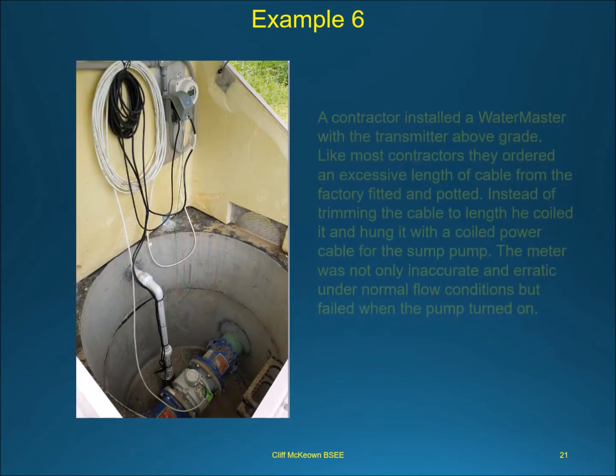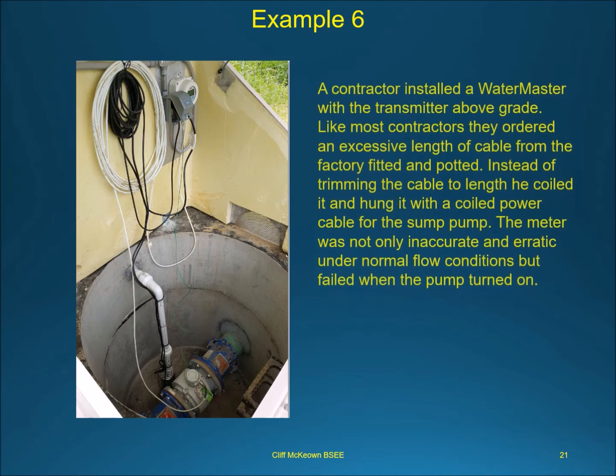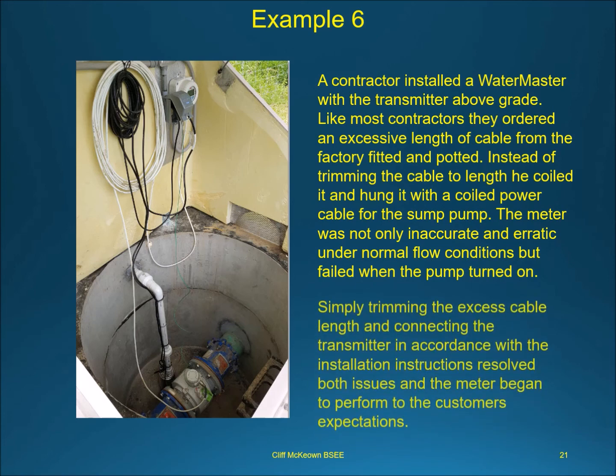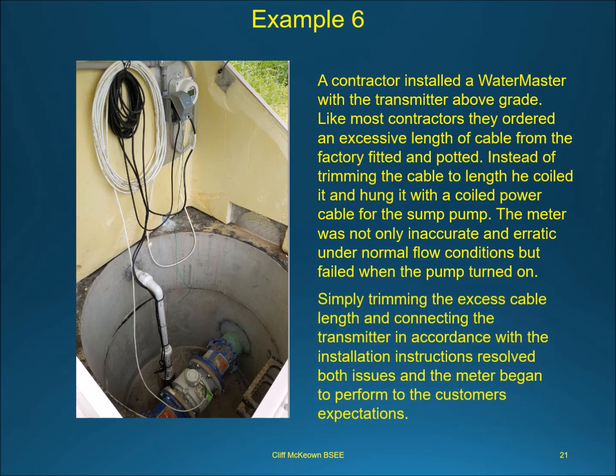A contractor installed a Water Master with the transmitter above grade. Like most contractors, they ordered an excessive length of cable from the factory, fitted and potted. Instead of trimming the cable to length, he coiled it and hung it with a coiled power cable for the sump pump. The meter was not only inaccurate and erratic under normal flow conditions but failed when the pump turned on. Simply trimming the excess cable length and connecting the transmitter in accordance with the installation instructions resolved both issues and the meter began to perform to the customer's expectations.